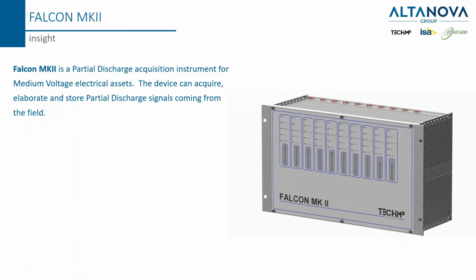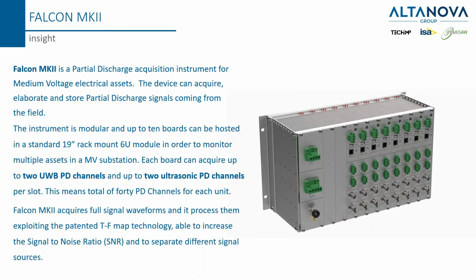Some insight. The Falcon Mark II is basically an evolution of the partial discharge acquisition instruments for the medium voltage asset. It comes in a 19 inch rack, and it is a modular system that can host up to 10 boards, mounted in a 6-unit high rack. Each board can acquire up to 2 ultra-wide bandwidth channels, for example for partial discharge, typically by means of the HFCT or the TEV, plus 2 ultrasonic PD channels per slot. That means in total, up to 40 partial discharge channels for each unit. This unit, the Falcon Mark II, acquires a full signal waveform and processes it exploiting the patented TF-map technology, able to increase the signal-to-noise ratio and separate different signal sources.